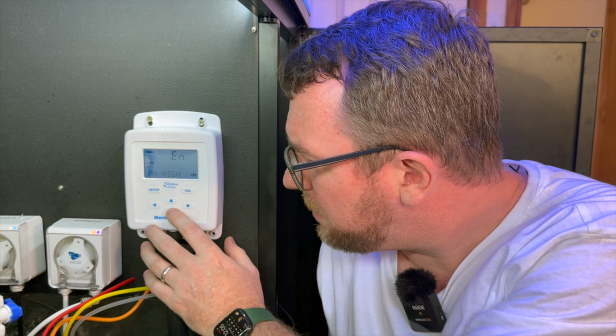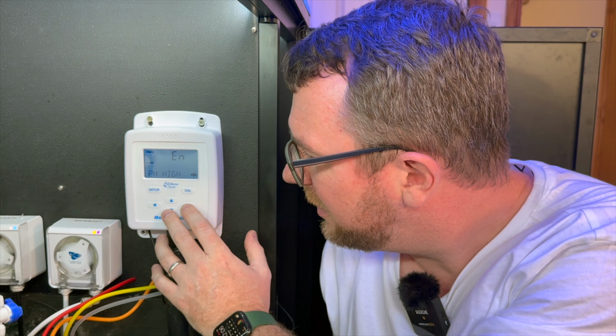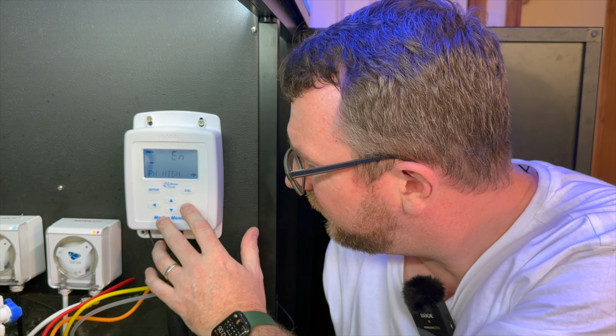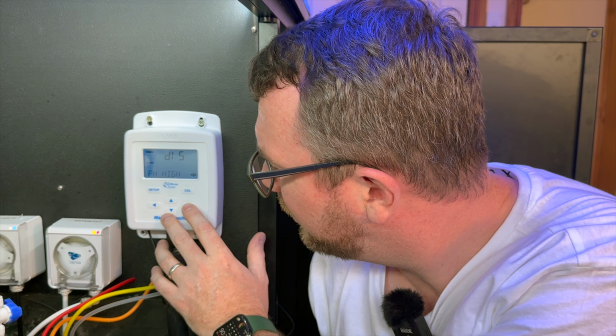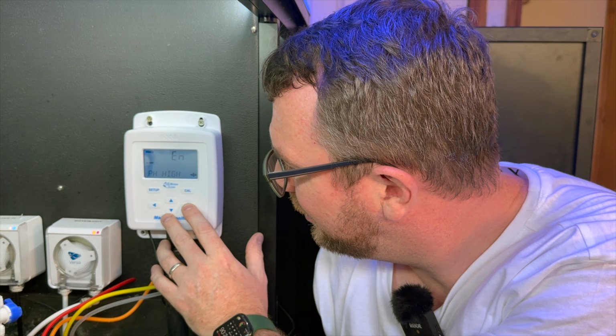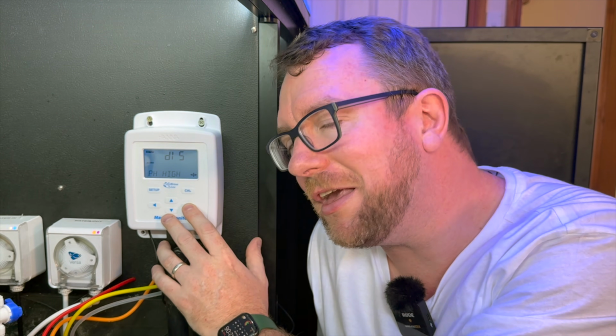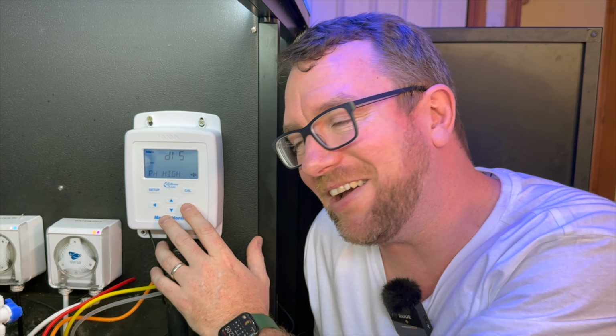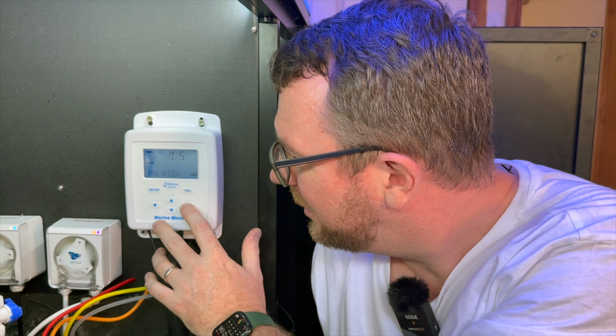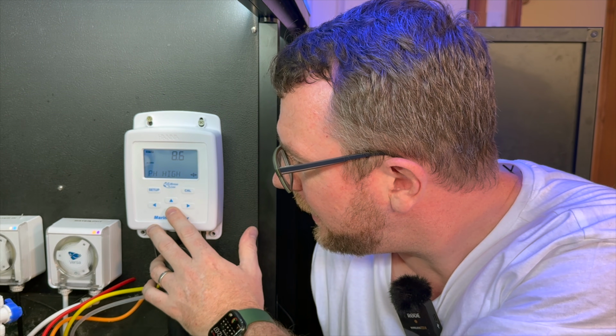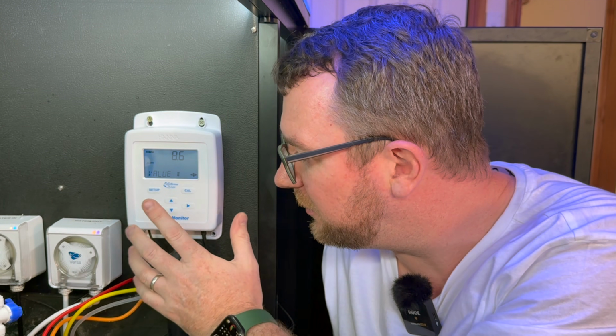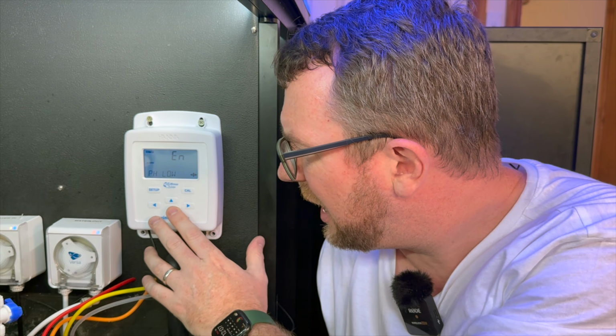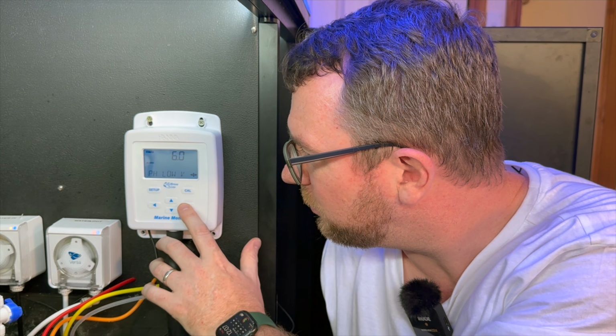And then we get to the pH high alarm, which is currently on. If I go across, I can set that to engaged or disengaged. That tricked me a little bit with the EN and the DIS, but it is engaged. Engaged, great. And the pH high is currently set to 8.6. So as soon as we get over 8.6, we should get an alarm. We've got pH low is engaged. It's currently set to 6.0. That sounds fair. In fact, let's raise that a little bit.